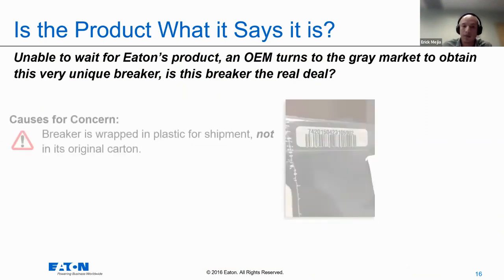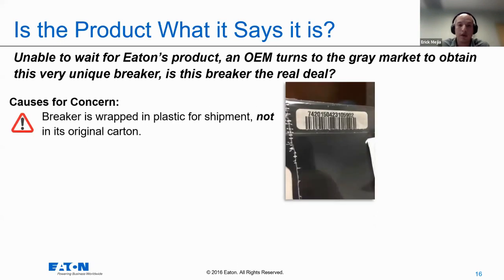There are a couple of causes for concern even if you purchase a breaker through an authorized distributor or a breaker broker. One huge concern is a breaker should not be wrapped in plastic — it usually comes in its carton, so that's a huge red flag to pay attention to.